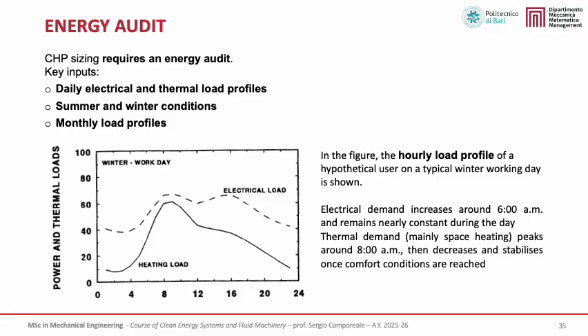The electrical demand starts to increase around 6 a.m. at the beginning of the daily activities and then remains nearly constant through the day. In contrast, the thermal demand, mainly associated with space heating, reaches its maximum around 8 a.m. when indoor spaces are brought to comfort temperature, and then gradually decreases, stabilizing during the rest of the day. These daily profiles are essential for understanding load simultaneity and for selecting an appropriate CHP operating strategy.